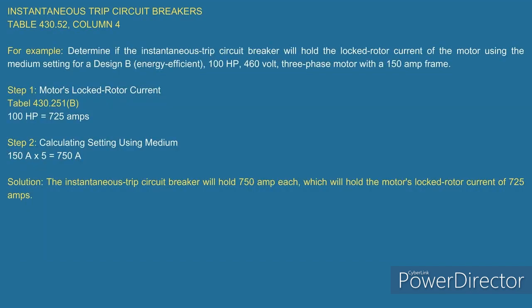What we're going to do here is an instantaneous trip circuit breaker, and we're going to ask, will it hold the locked rotor current of the motor using a medium setting? So we're going to do a medium setting. You can go 5, or the next one, which is 7, all the way up to 10. We're just going to do the 5 here. It's going to be a Design B energy efficient, 100 horsepower, 460-volt three phase motor, and it has a 150 amp frame.